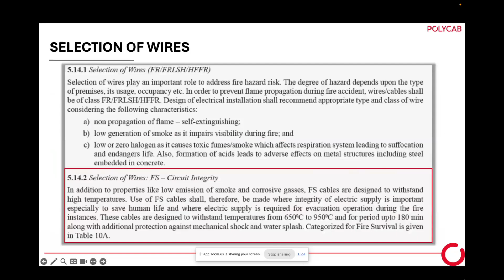One more thing I should mention - if you see the Polycab cable, there is an LPCB approval. Many manufacturers are manufacturing fire survival cable, and customers are taking those cables, but the customer doesn't have any testing arrangement to cross-check whether these cables are really fire survivable, or whether they will pass fire survivable testing like 950 degree temperature for 3 hours. Customers don't have that infrastructure.